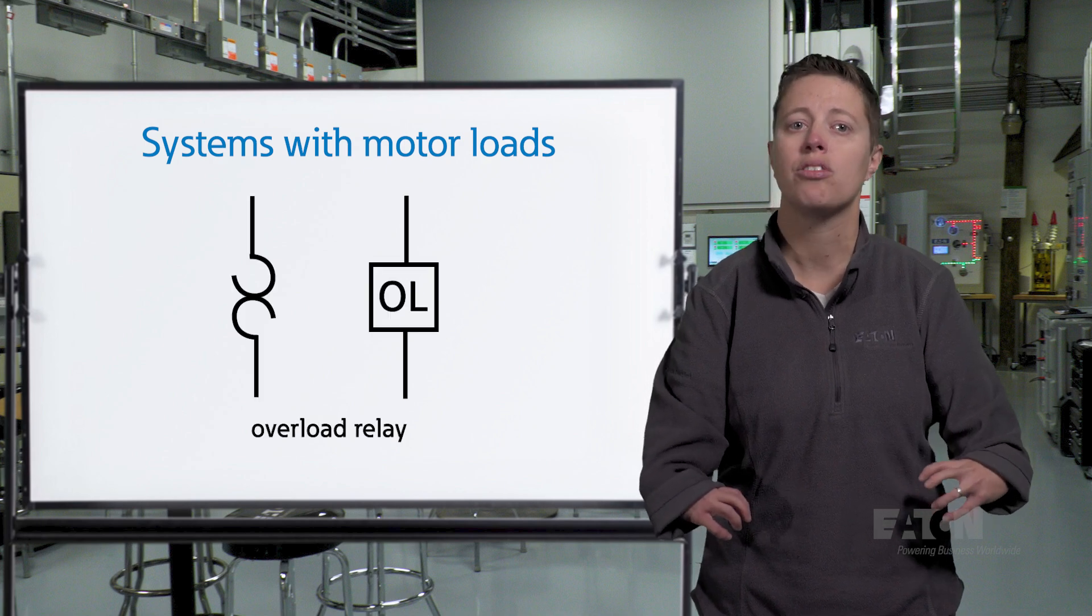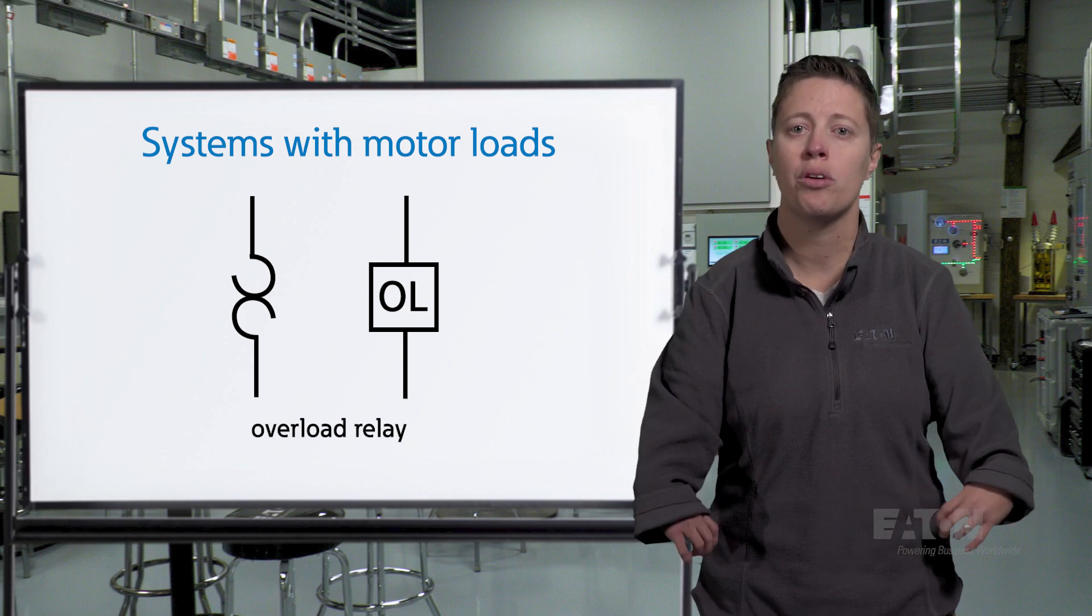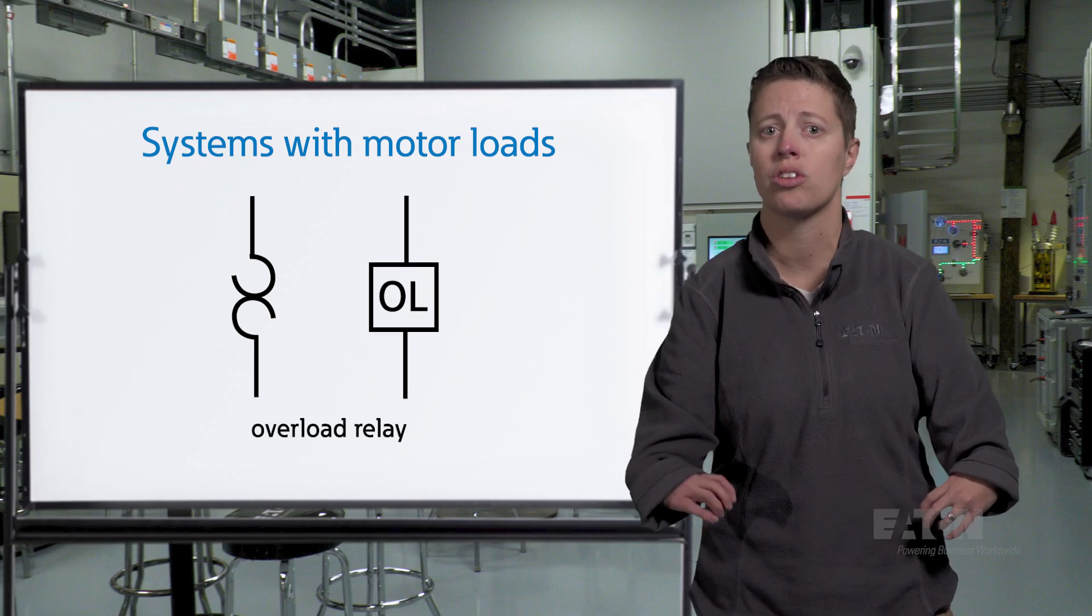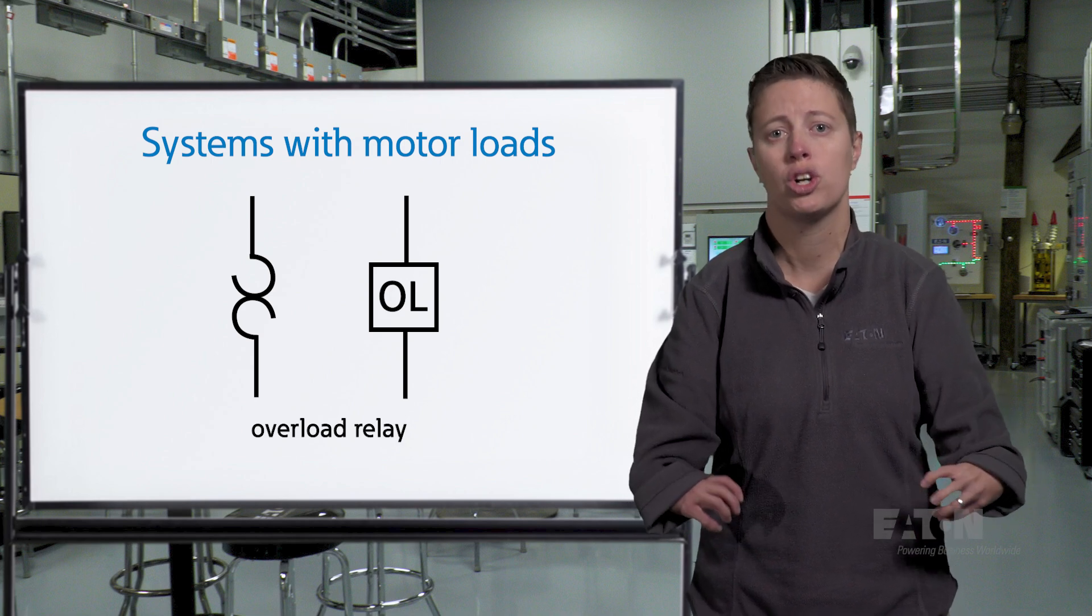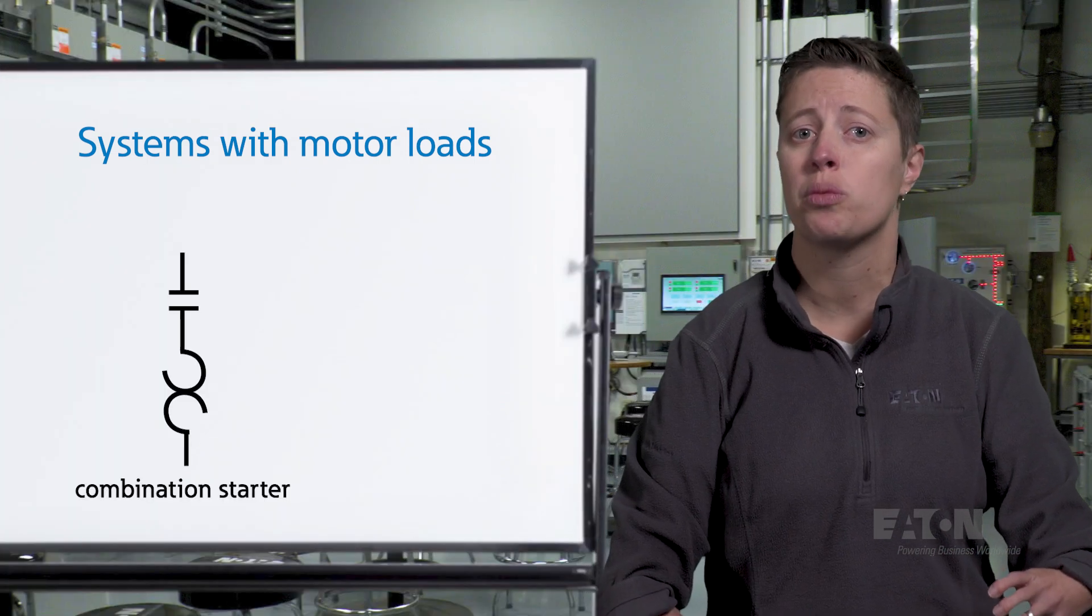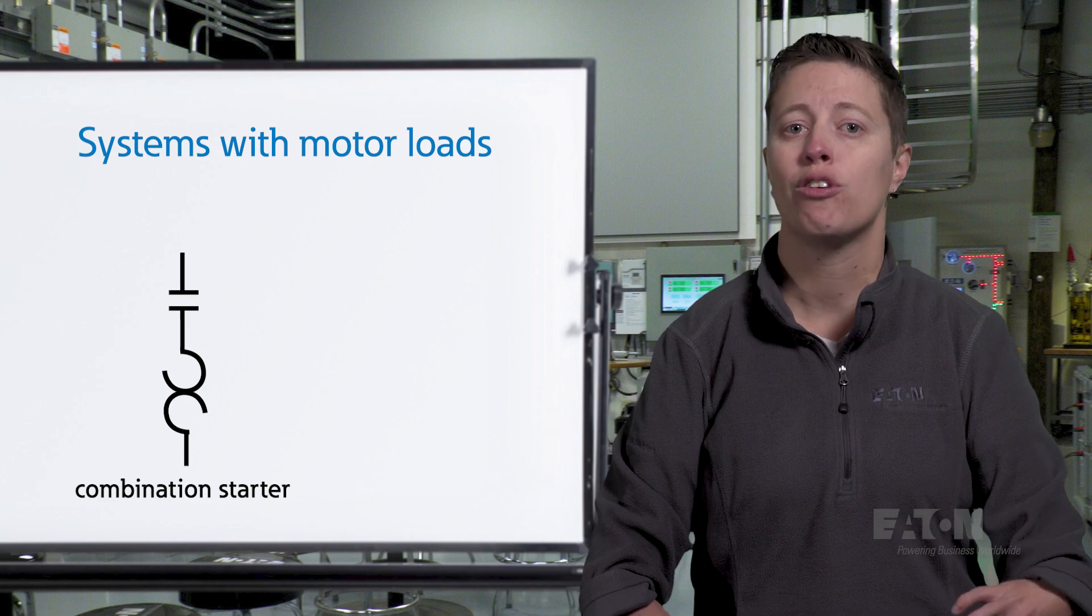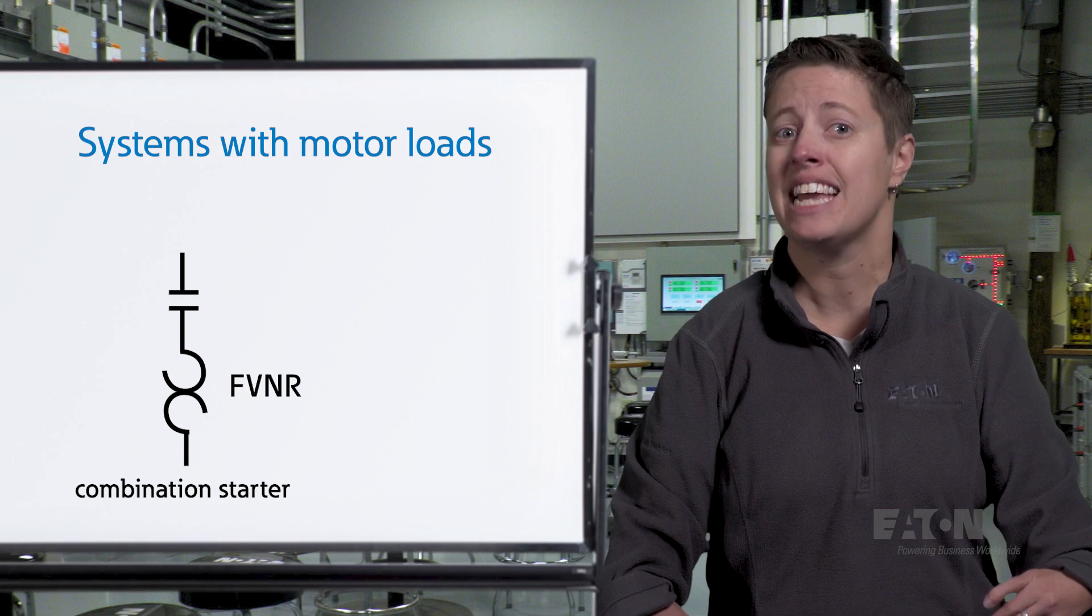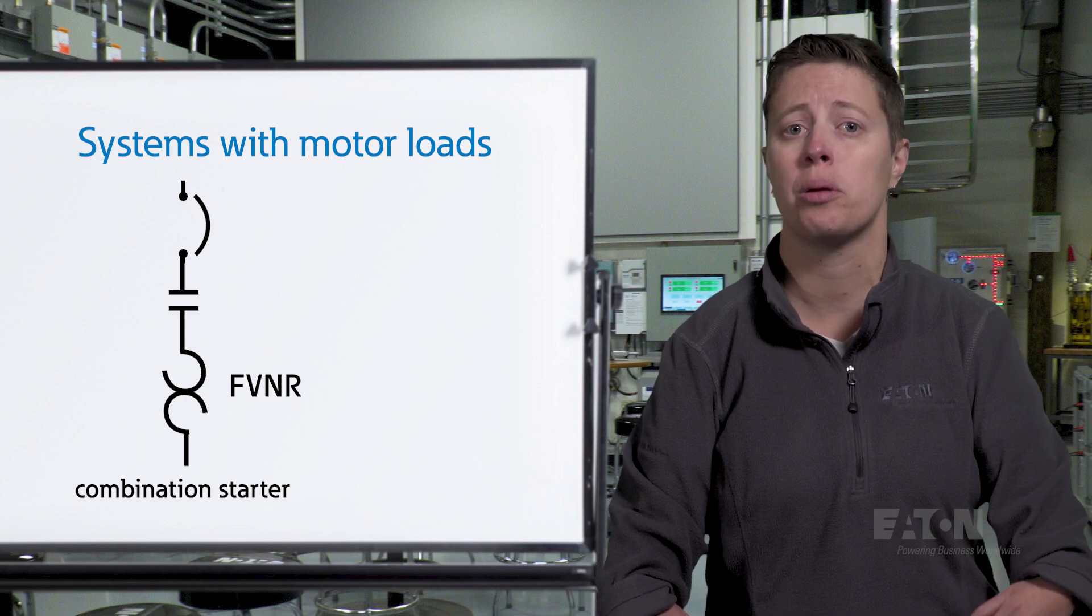An overload relay is noted by two linked, broken semicircles or a block labeled OL. An overload relay protects motors from overheating due to prolonged overcurrent conditions, called overloads. This is different than a circuit breaker trip unit, which provides shorter term short circuit protection, as well as overload protection. A contactor in series with an overload relay represents a combination starter. In this example, we see a full voltage, non-reversing starter. The starter may be labeled FVNR on the single line and may include a switch or circuit breaker disconnect upstream of the contactor.